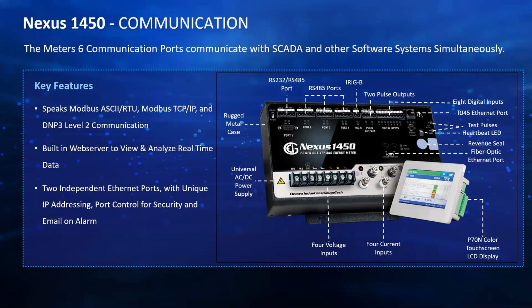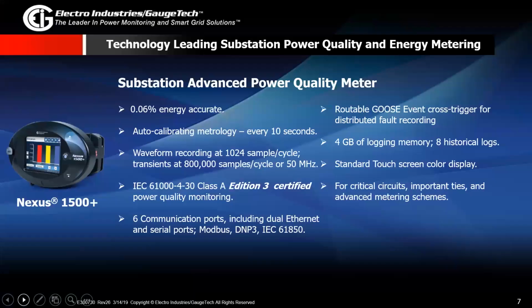So next is the Nexus 1500 Plus meter that I mentioned. This is a substation advanced power quality meter. This will also give you 0.06% energy accuracy, and this meter actually follows a metrology where it auto calibrates every 10 seconds. So this ensures that over time, with equipment, the accuracy may drift for a number of different reasons, for weather or harsh conditions. But this meter will auto calibrate itself every 10 seconds, making sure that it continues to be accurate over long periods of time. It can also record waveforms at 1,024 samples per cycle, and it can capture transients at up to 800,000 samples per cycle.